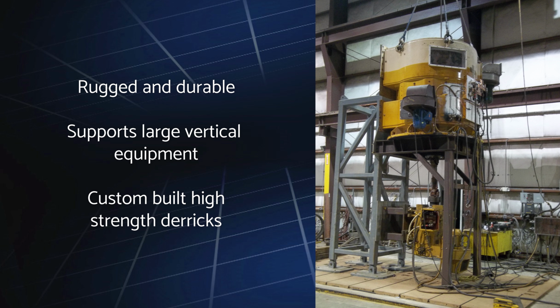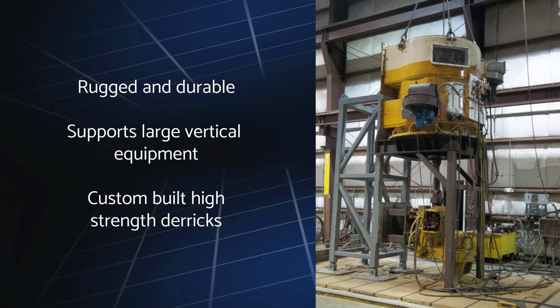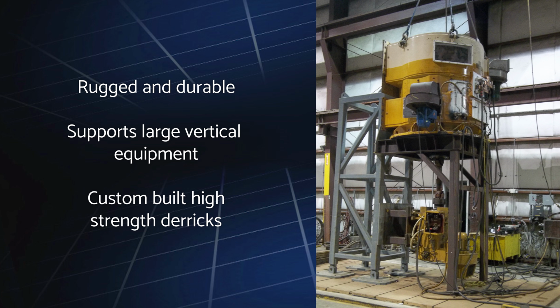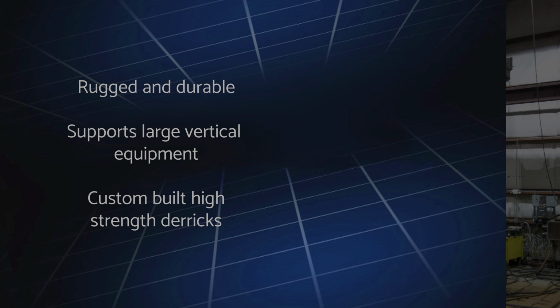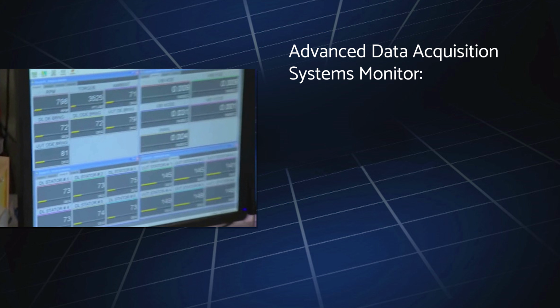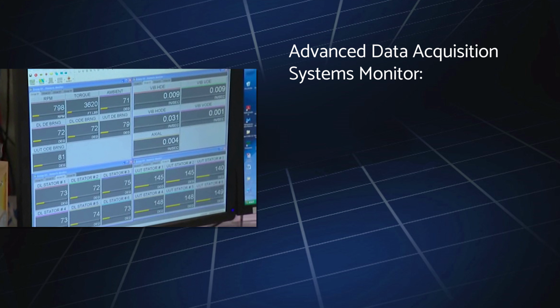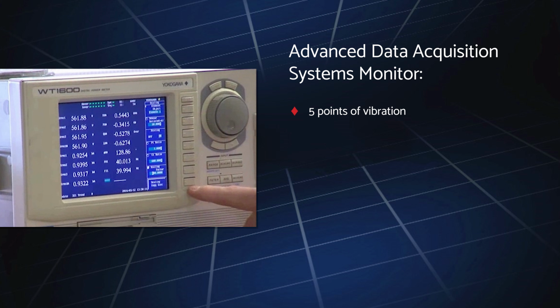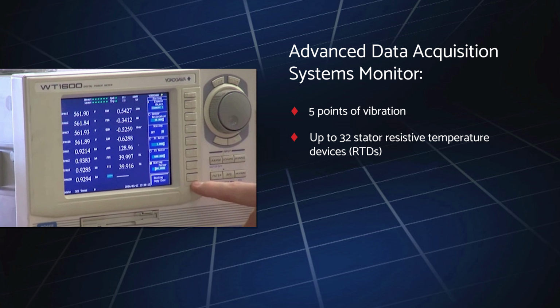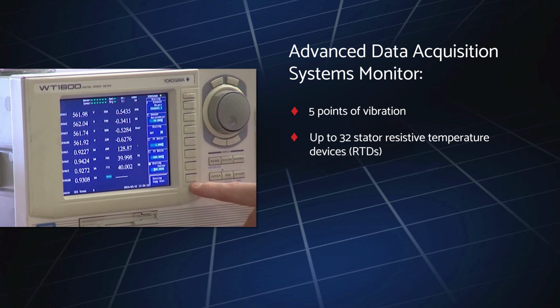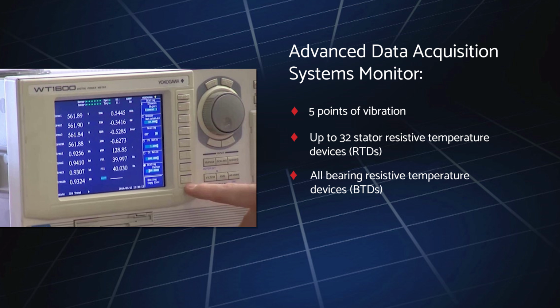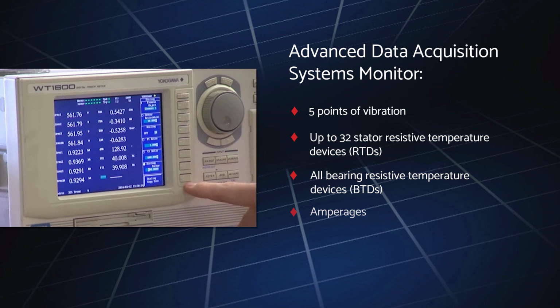Built for heavy equipment, the stand is rugged and durable, easily accommodating large vertical motors and generators on our own custom-built high-strength derricks. Advanced data acquisition systems monitor 5 points of vibration, up to 32 stator resistive temperature devices, all bearing resistive temperature devices, amperages, and voltages.